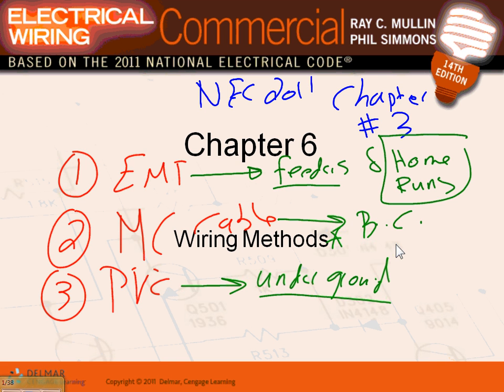Let's say you're running up the side of the building. Now, going up high, you would stay with the PVC though. In a case like this, if you're outside with the service, I would use PVC Schedule 80, or the best is rigid metal conduit. So you can switch from... Yep, absolutely, you can switch. You can have a fitting that takes you from PVC into rigid. Okay, and then obviously a good sealer. Yeah, sealing and all this good stuff.